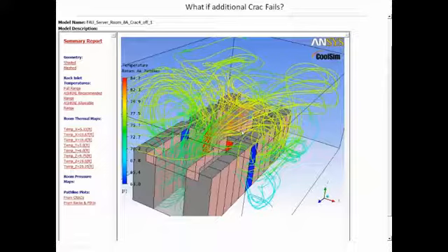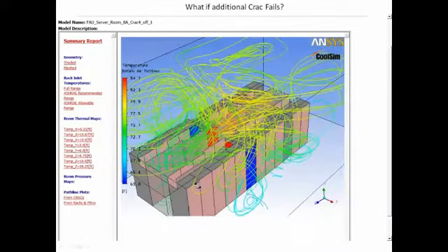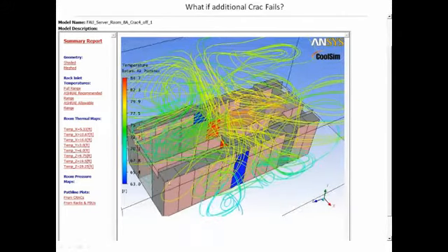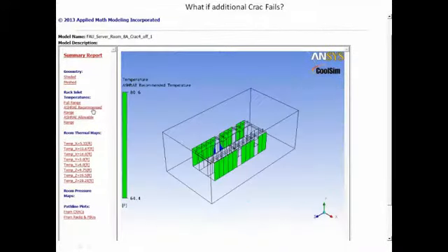And it's important to understand what these failure modes look like so that you have a plan in place of when a unit's going down for service or when a unit's going down because of a failure mode. You have an idea of what to do. In this case, what you'd have to do is run in and start pulling off the containment right away, or the servers would starve.